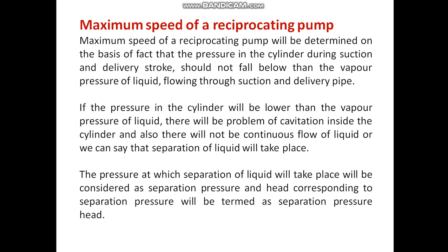And the pressure at which the separation takes place is called as the separation pressure, and the corresponding pressure head is called as separation pressure head. And for doing this, we'll consider suction and delivery stroke separately. So this is your indicator diagram, by considering the combined effect of acceleration and friction. So you take the suction stroke. Considering the suction stroke, during suction stroke, the variation is A dash, G dash, B dash. So here the low pressure is at A dash, the point A dash, that is the beginning of suction stroke.